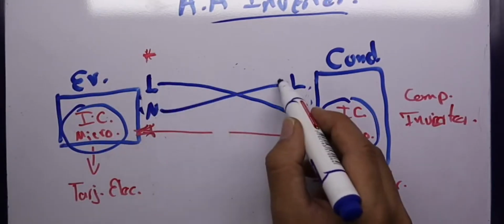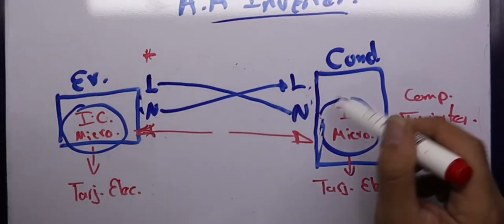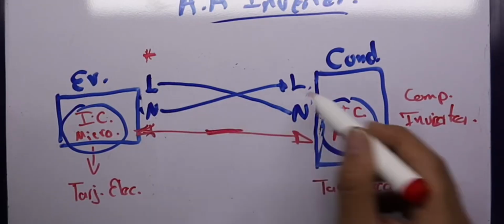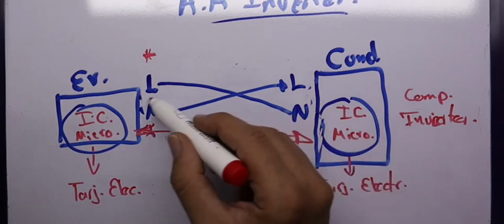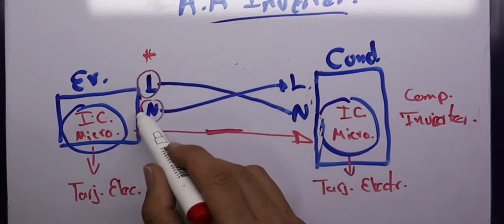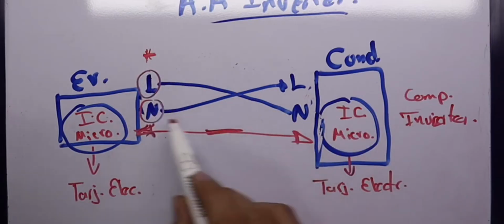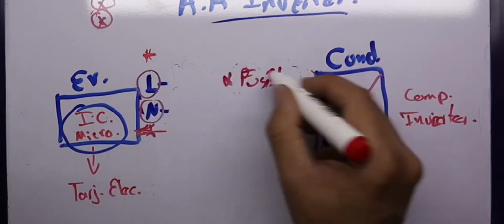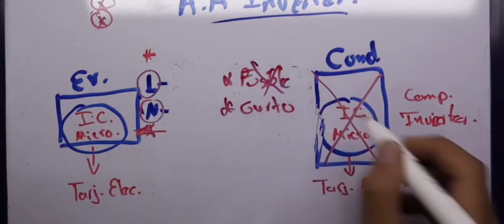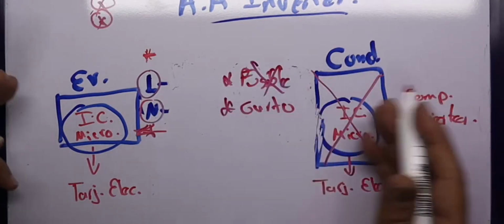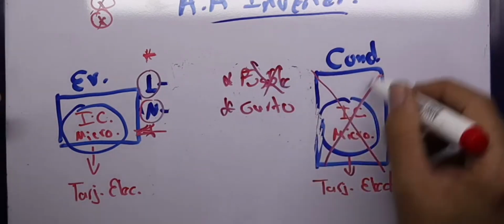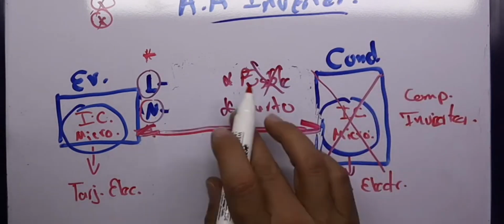Another thing could be that the cables, the technician has connected them wrong. Yes. If the cables are crossed, it will also mark a CH5 error, because the electronic card could be reading anything. Another cause is that the fuse is blown, or that the condenser unit card is already shorted. So those could be the possible faults for which the equipment throws the CH5 error at me.